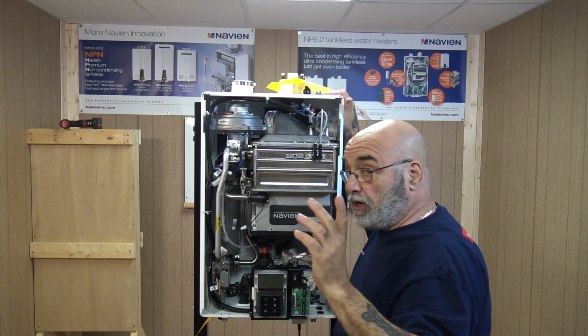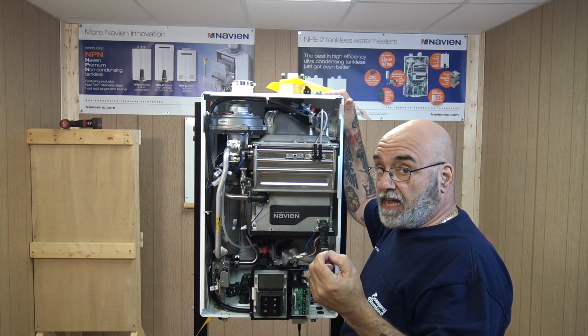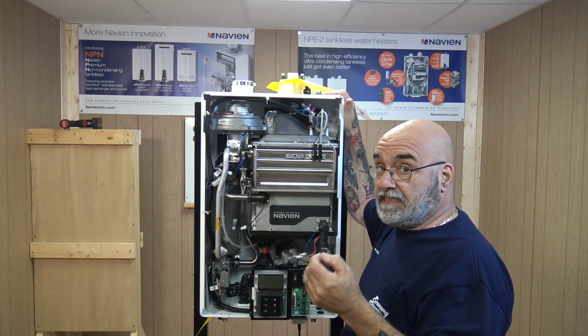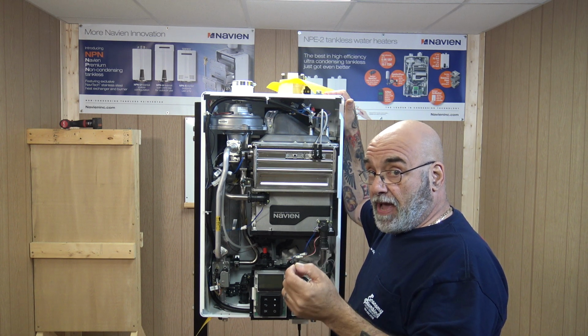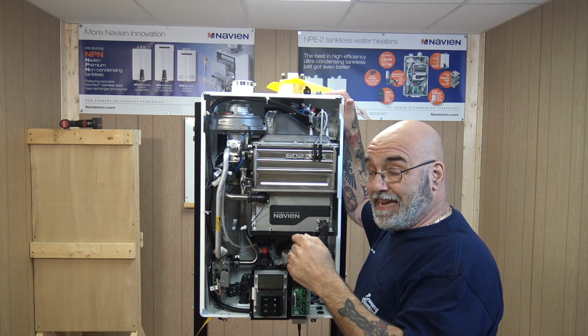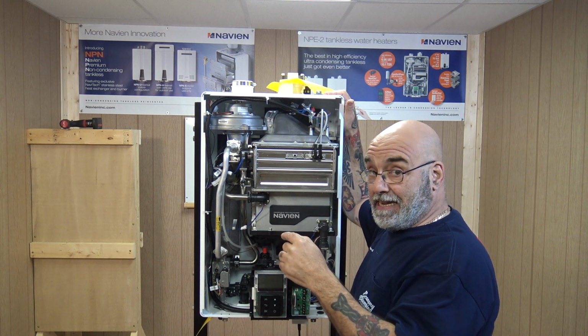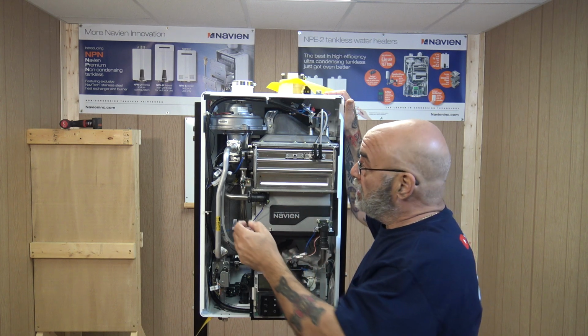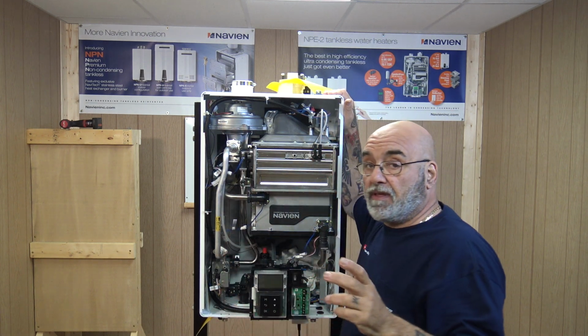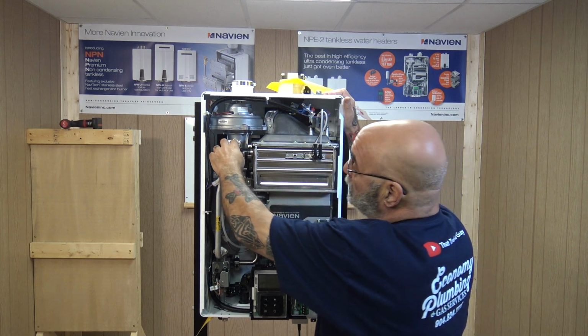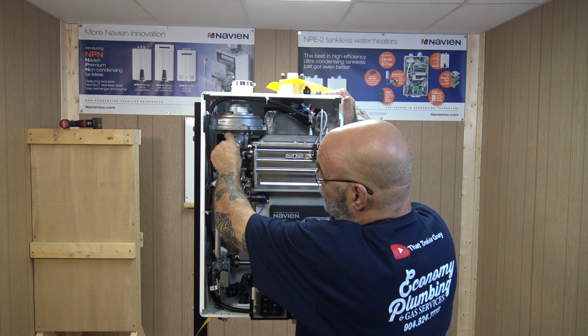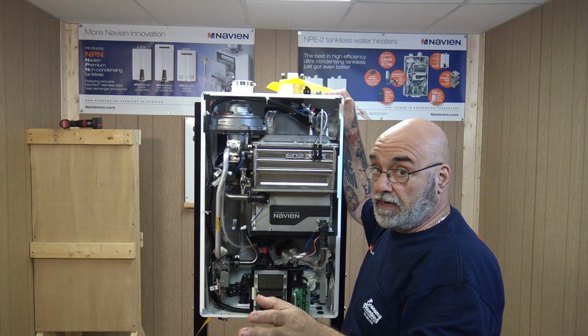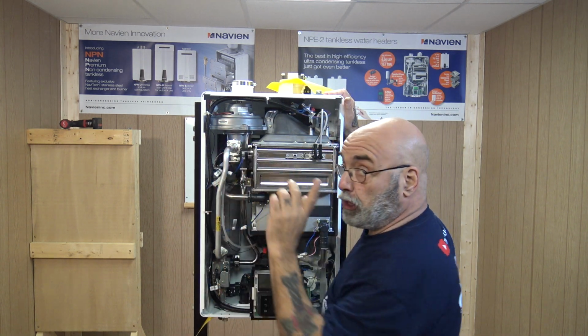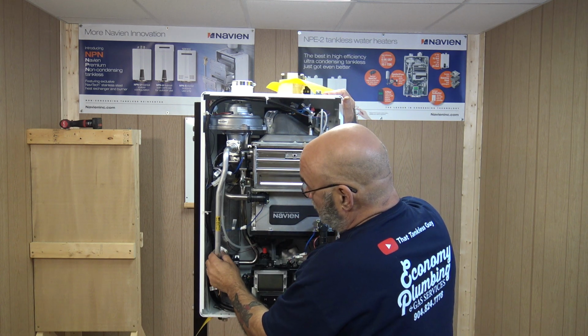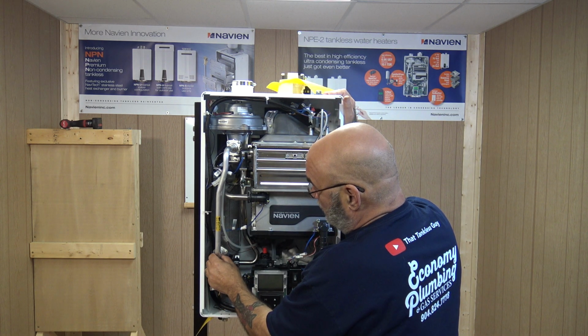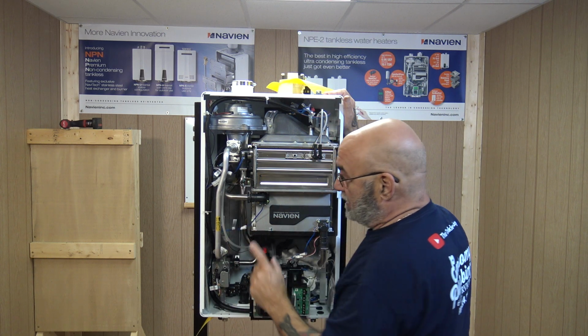It's directional, it only goes in one way. Always check the orifice and make sure it says LP on it, that somehow an NG orifice didn't get in. I've had that happen. So always visually check the orifice. Put it in, put the screws on, and then you put this all back together. You're going to put these 4 screws in first. Doesn't matter how you take them apart, but you're going to put these 4 in first loosely. Then you're going to manipulate this. There's a little bit of movement on the gas valve in this. Catch these screws, then tighten them up.